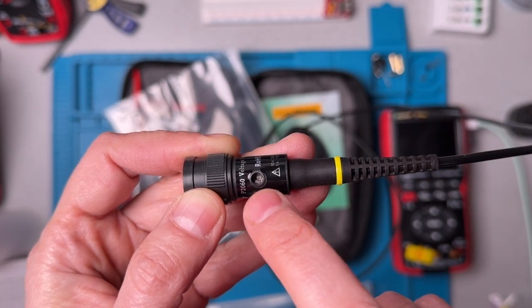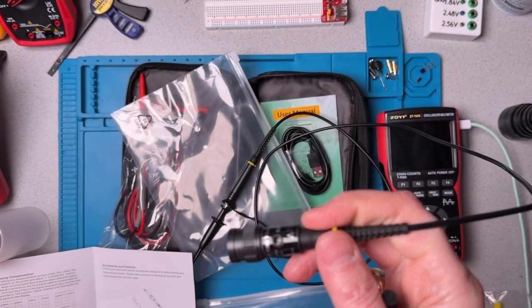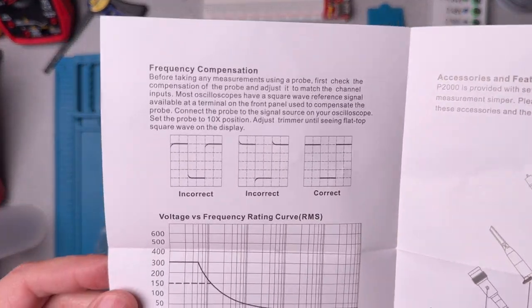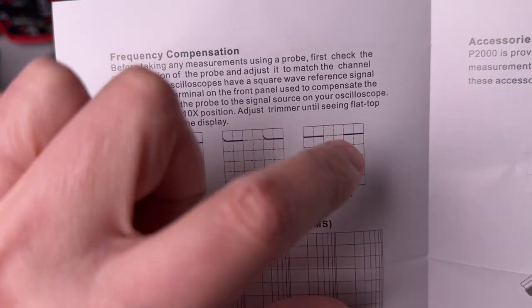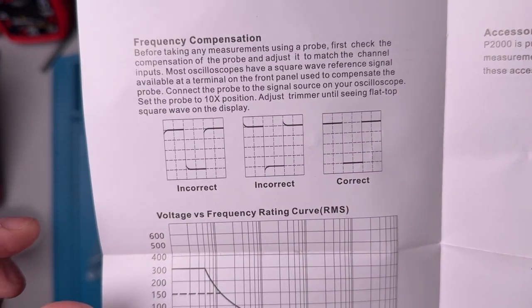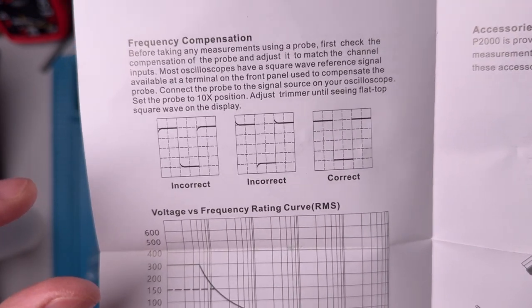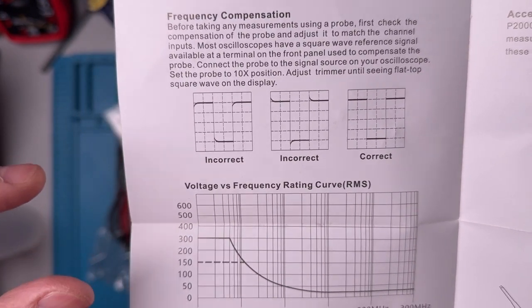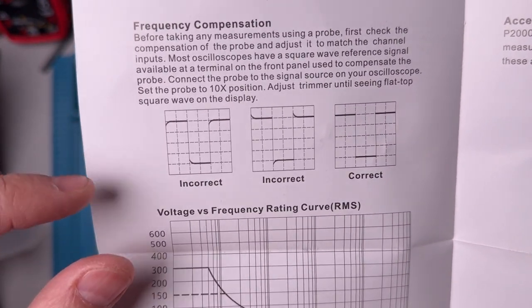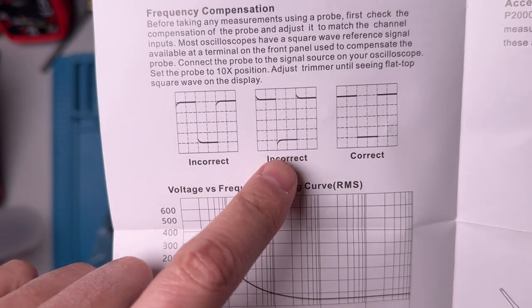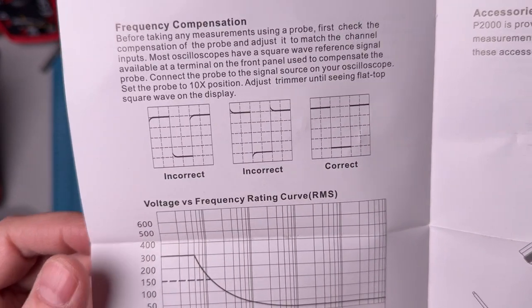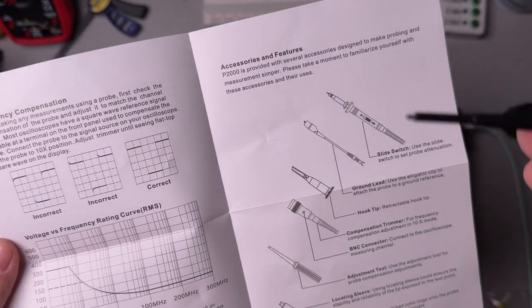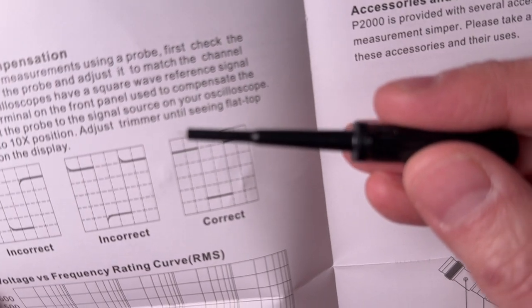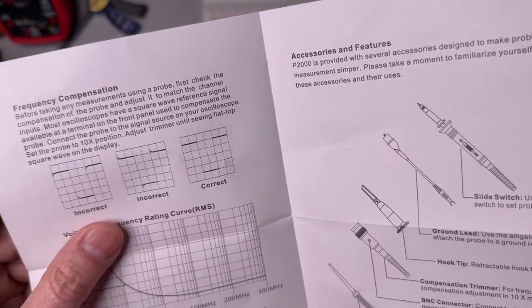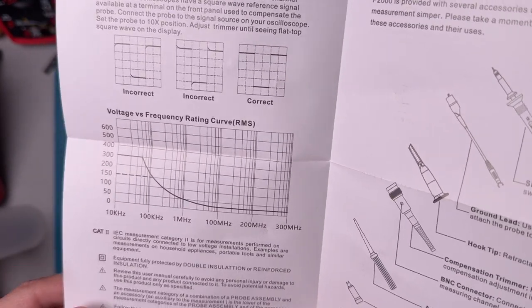So it turns out, and this is learning for me, this is a trimmer for frequency compensation. And if we have a quick look at the instructions, it talks about how we can make sure that we've compensated properly for the square wave signal and the adjustment of the oscilloscope probe. And so we can see what incorrect waves and some correct square waves look like, and what we should see. And so that trim pot and this little screwdriver are intended to allow us to perform the tuning of the probe before we make use of it.